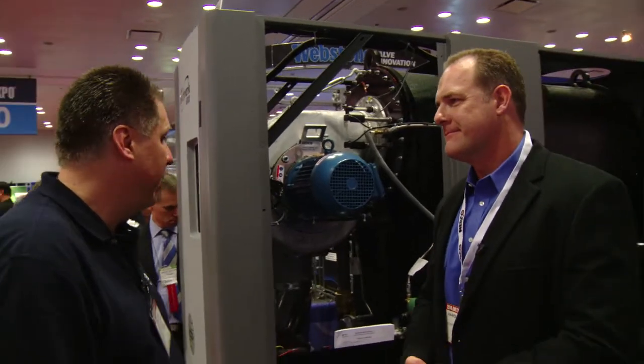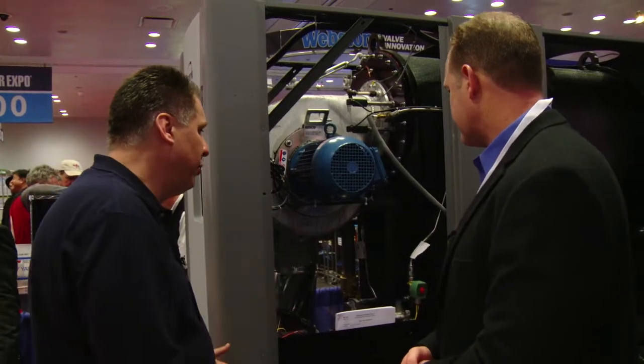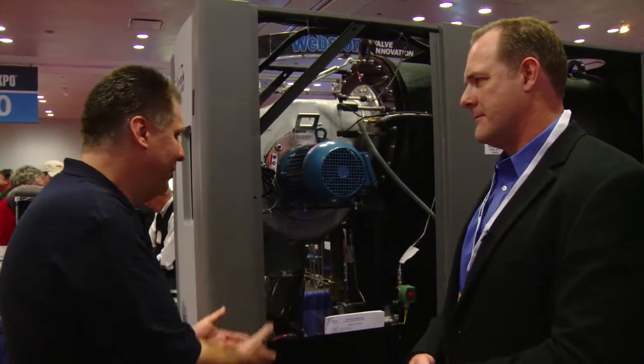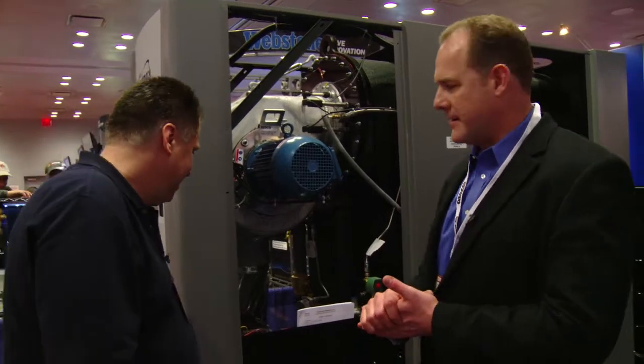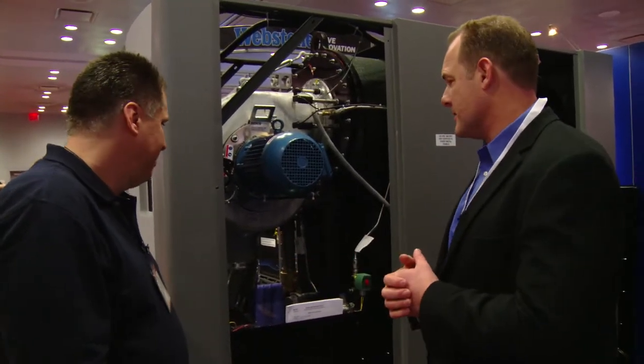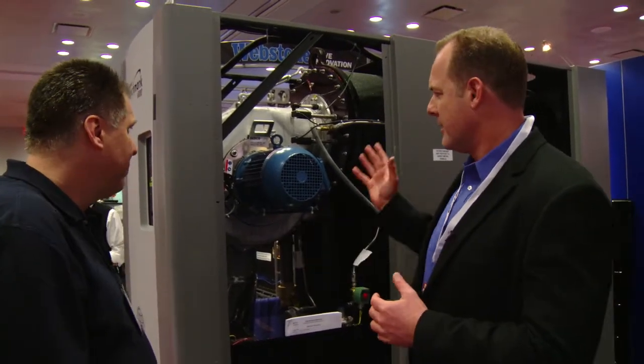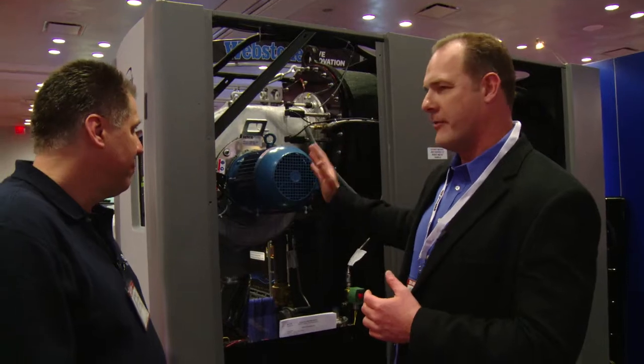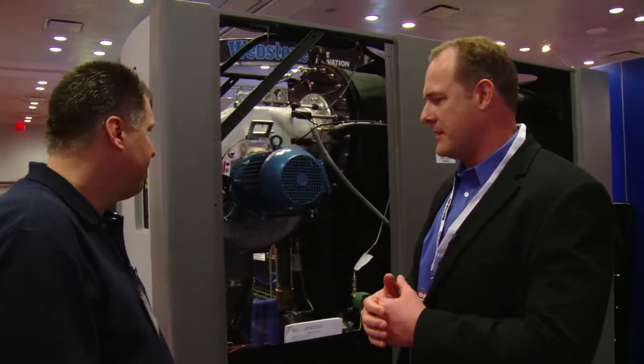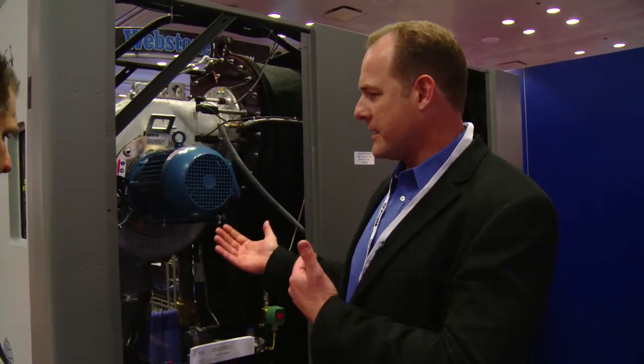Now, I was a service technician for 16 years before I started my company. What I see here looks like it's easy to service. I can get to all the components, I can get my tools in there. I'm not standing on my head to service that. Was that designed into this boiler? This was absolutely designed into this. So for our service contractors, even installers, all of AERCO's benchmark boilers from 750,000 up to 6 million are 100% serviceable from either the front or the back. And we designed that specifically so in two scenarios. Number one, ease of serviceability, and then for installation, we can actually put two boilers side by side with zero sidewall clearance. Wow, that's a unique feature.